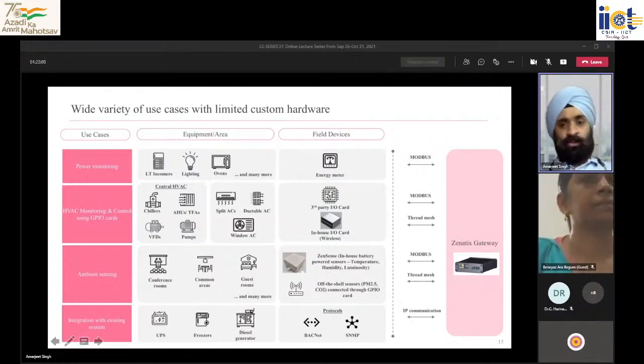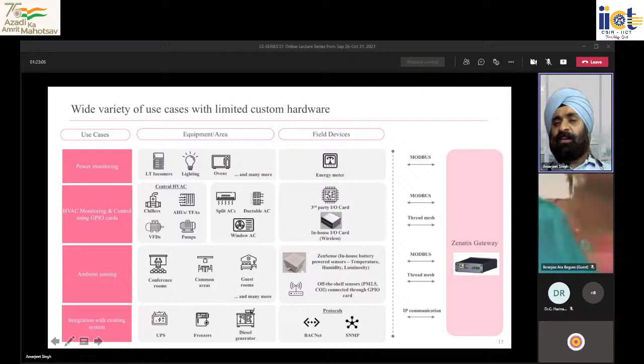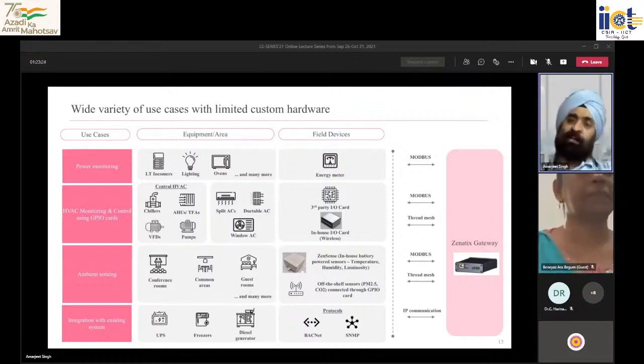And then you are also talking over standard protocols like BACnet, SNMP, and Modbus. So essentially, with only a small set of custom hardware, you are able to connect a wide variety of air conditioning equipment, all the way from split ACs to ductable ACs to VRVs to water-based systems, which may have AHUs.